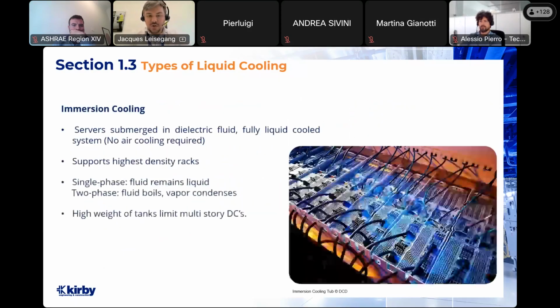So next we're looking at immersion cooling. Immersion cooling is where the servers are fully submerged in a dielectric fluid. The servers are fully liquid cooled, so there are no air cooling requirements. The whole server, including all the ancillary components, has all of its heat transferred into the fluid. This supports the highest density racks. As we discussed previously, you can do it as a single phase where the fluid remains a liquid, or as a two-phase application where the fluid boils off and the vapor condenses and drops back into the bath. There are limitations and challenges associated with immersion cooling, one of them being the weight of these tanks, which would be one of the limiting factors.